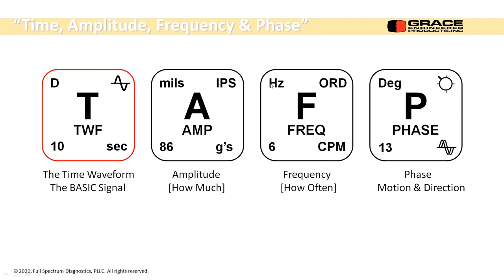Frequency, there's hertz, which is cycles per second. There's orders, so it would be one times, two times, three times, four or five orders of shaft rotation. So it's just normalized frequency. And CPM and RPM are cycles per minute and revolutions per minute. Frequency is how often the fault occurred, or if we go from the time waveform to the frequency domain, it's going to show up as a peak in our spectrum. And that peak is also going to be alarm criteria, probably as an overall level and as a spectrum band alarm. And we'll get a little bit more into that as we go.